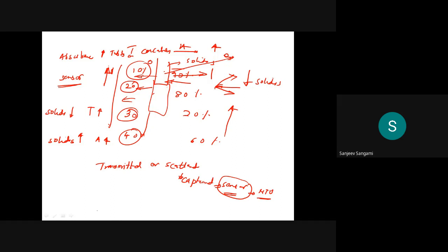For that we have to prepare standard NTU solutions. We'll prepare 0 NTU, 10 NTU, 100 NTU and 1000 NTU. First, 0 NTU is nothing but distilled water.